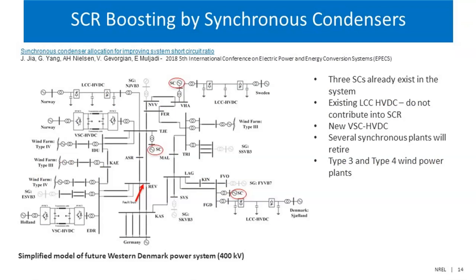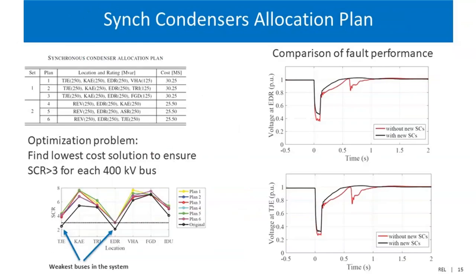So we conducted an analysis on what is the best way to maintain the voltage stability and the system strength for this particular system, which eventually ran into a simple optimization problem: to find the lowest cost solution to ensure that the short-circuit ratio criterion on each bus is met, which was short-circuit ratio above 3. So there are a number of scenarios in this table, and the associated cost and the MVAR ratings for synchronous condensers.